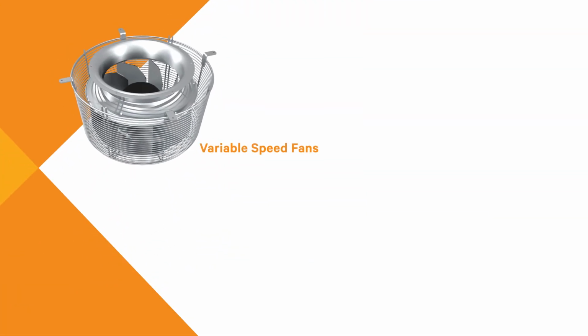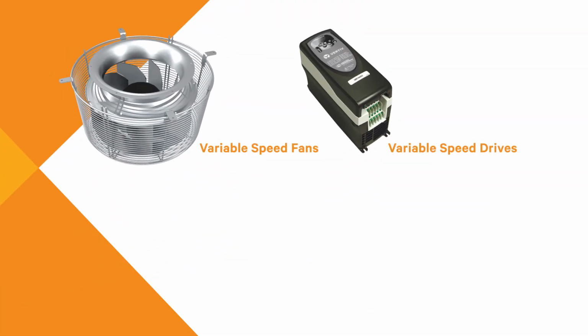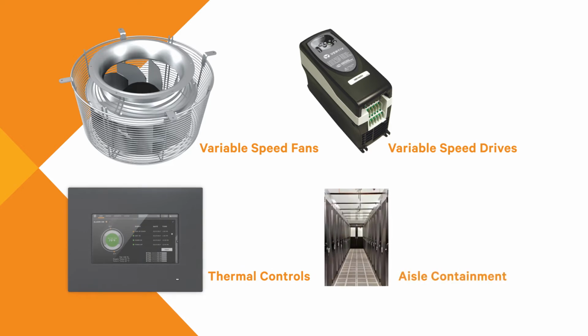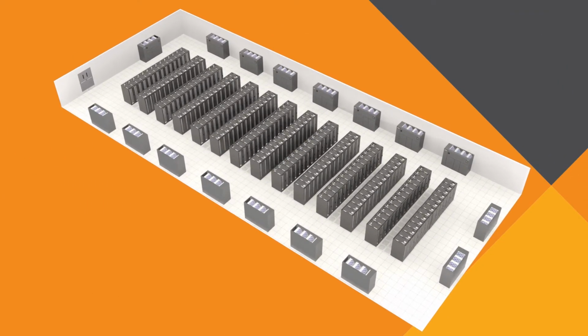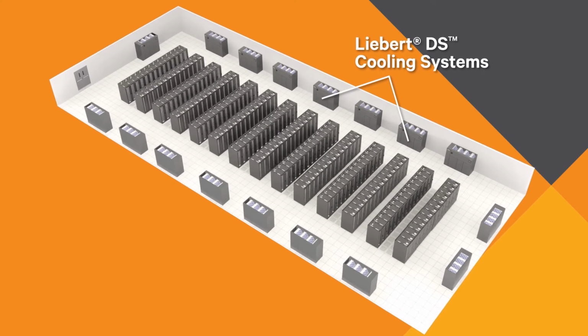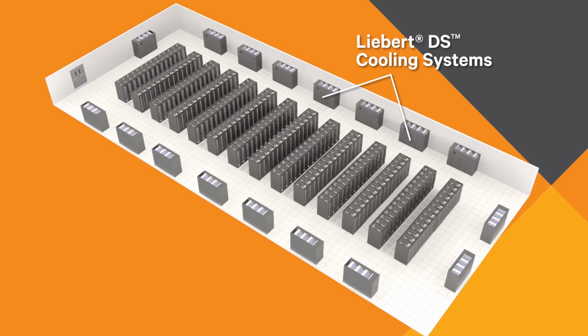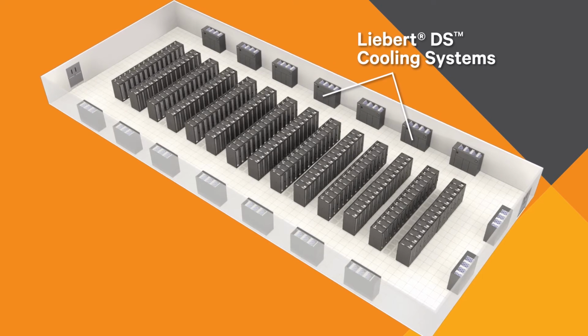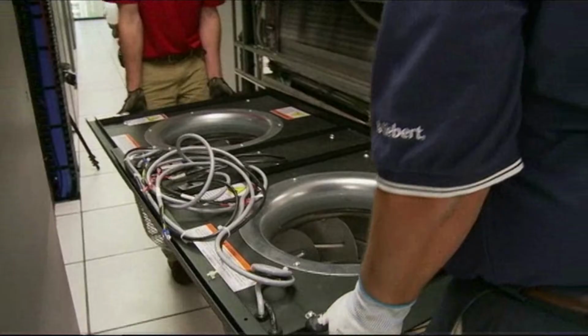Adding variable speed EC fans or variable speed drives, advanced controls, and containment can provide a fast payback. Let's look at the numbers, starting with 10-year-old Liebert DS cooling systems as our base case. We'll consider a 1 megawatt data center with 16 of the older cooling units.